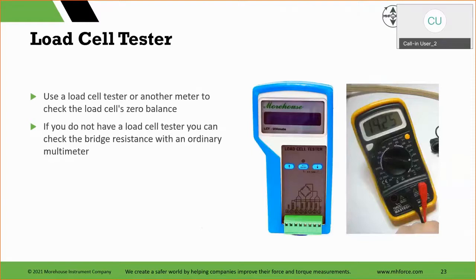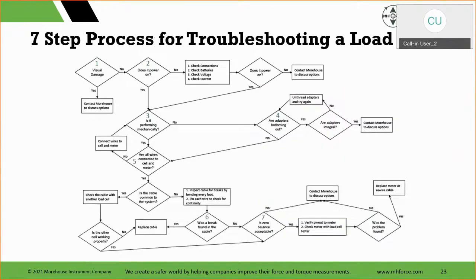So, other things: use a load cell tester or another meter to check the load cell zero balance. If you do not have a load cell tester, you can check the bridge resistance with an ordinary multimeter, as just shown, where you can check A and D, B and C, maybe E and F. And back to the 7-step process again, just as a wrap up. Visual damage, does it power on? Is it performing mechanically? Yes, no. If it's not, are adapters bottoming out? There are some tricks and tips there.